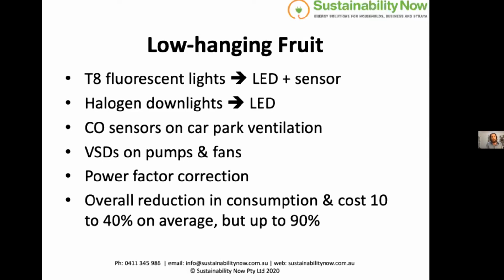Carbon monoxide, or CO, sensors on car park ventilation systems. The Australian standards say a car park ventilation system should run 24 hours a day, 7 days a week, unless you can monitor the air quality and adjust the fans based on that. It's uncommon to find car park ventilation systems running 24 hours because it's just so expensive. In most cases they've been put on a timer to coincide with perceived peak vehicle movements, which is more than likely wasting electricity unnecessarily.